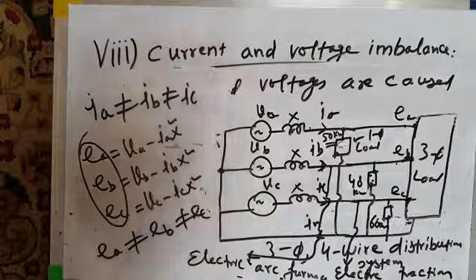Now what will happen if the three-phase voltages applied to three-phase loads are unbalanced? This is your three-phase voltage which is supplied to a three-phase motor, for example. Now this EA, EB and EC, they are not equal. The voltage applied to this three-phase motor is unbalanced. What will it result in? We will study in one of the future lectures that if these voltages are unbalanced, they are not equal, it results in large heating in AC motors. It may be an induction motor or a synchronous motor. So there will be large heating in AC motors, which will decrease its efficiency.